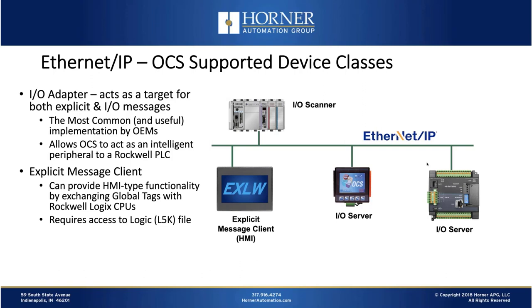The next device class supported by Horner all-in-one controllers is the explicit message client, which can be thought of as an HMI class. With this functionality, an OCS can have access to the global tags in the Rockwell Logix processor. That data can be read and written as needed, tied to standard objects on the graphics screen. Taking it one step further, you can map those Rockwell tags to internal OCS memory addresses, enabling more than just HMI functionality — you can use that data in logic, perform data logging, WebMI web serving, and more.